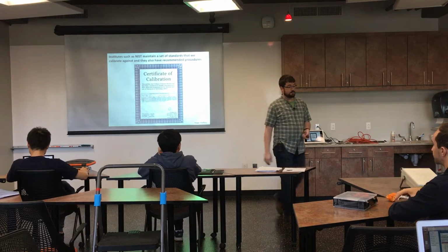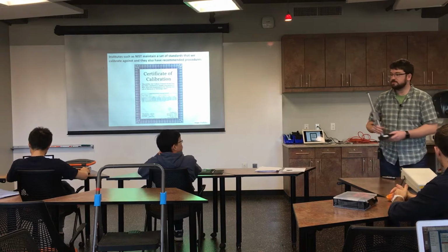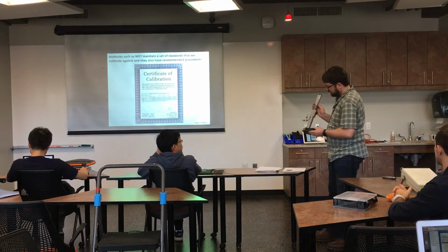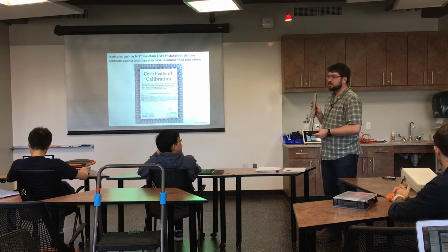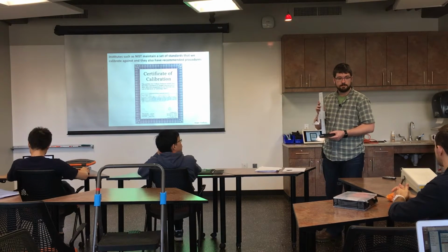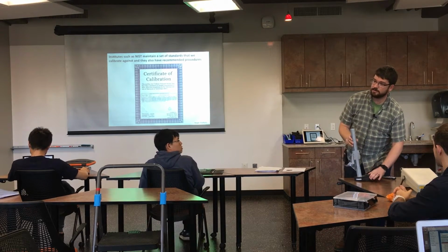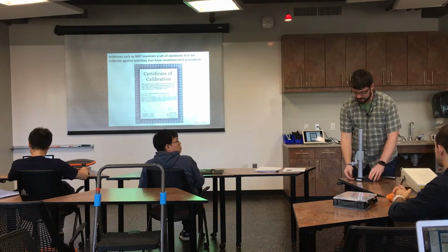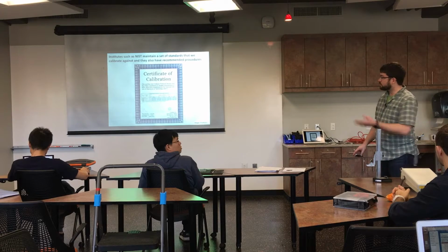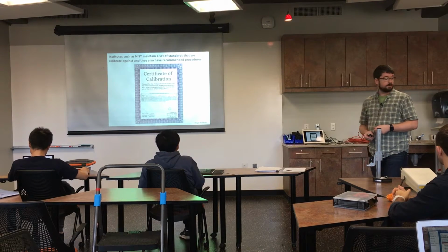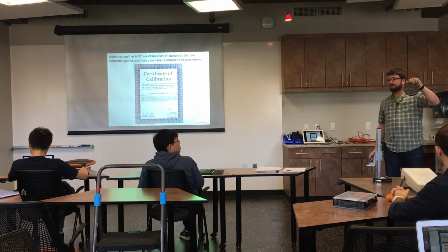We've got several, for example, this one. Those of you that calibrate the displacement transducer today will be using this. This is a vernier height gauge. So something like this with a certificate from NIST is going to run you about $2,000 or so. And this is very, very accurate. You can get down to about 1/1000 of an inch positioning with this in height above the base. For load cells, I'll show you a picture of what we would normally do. What you're going to use today are these not NIST calibrated 5-pound fitness weights.